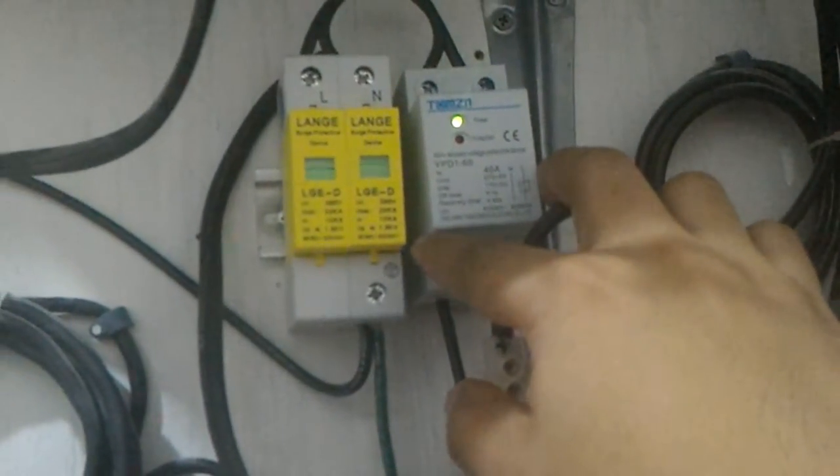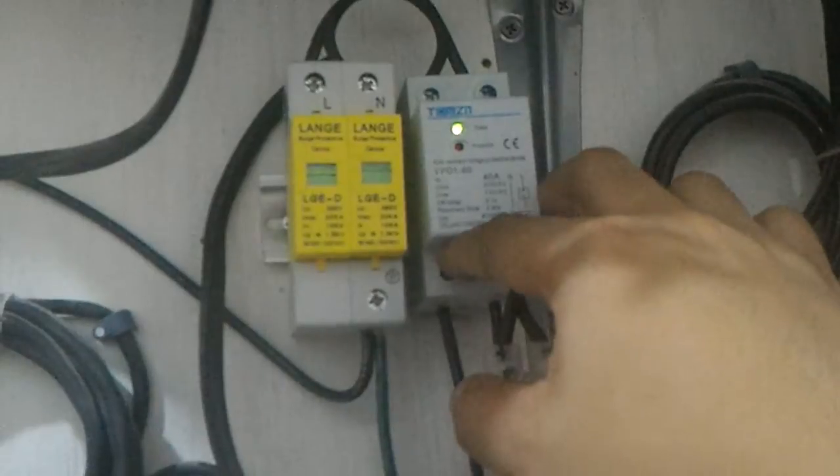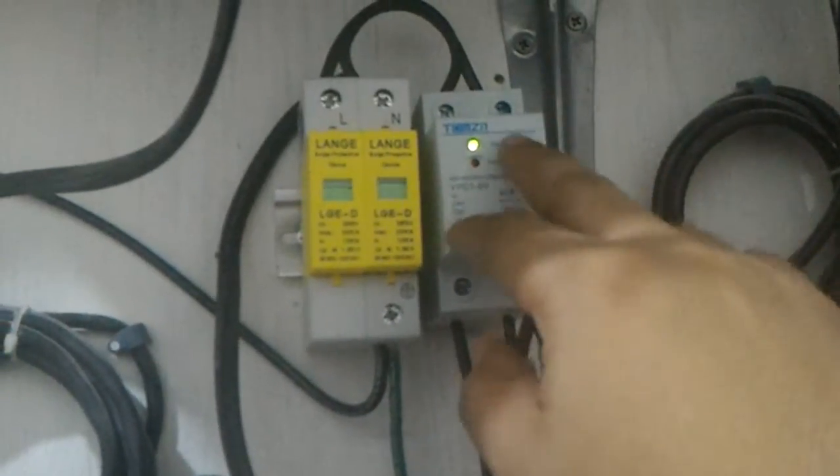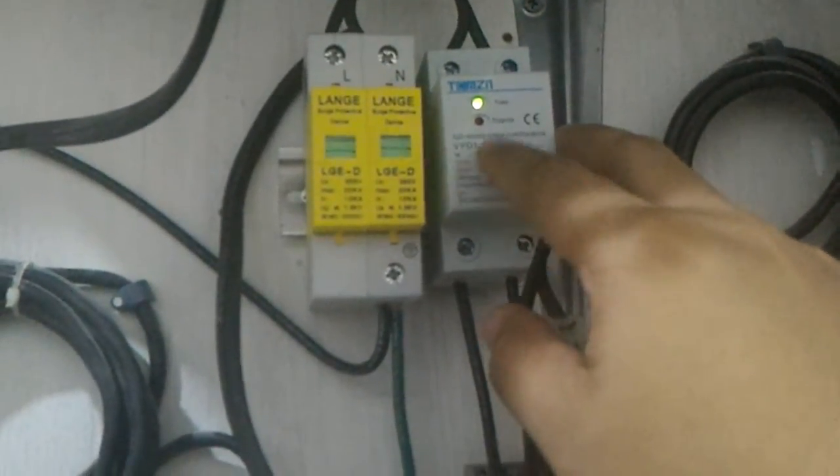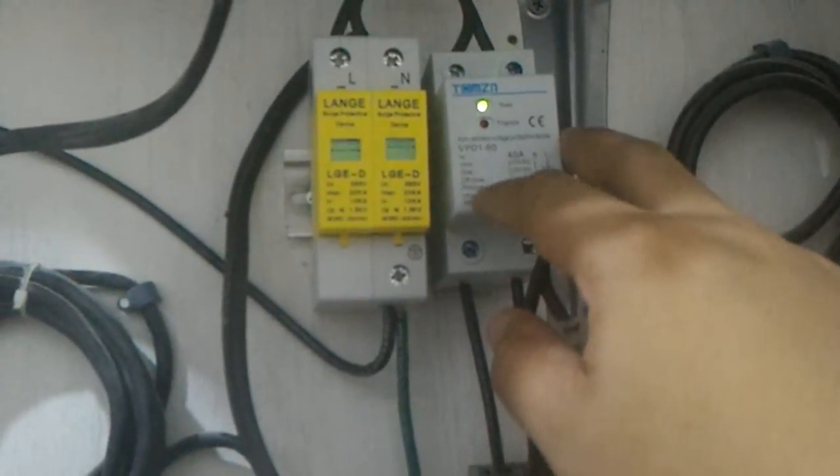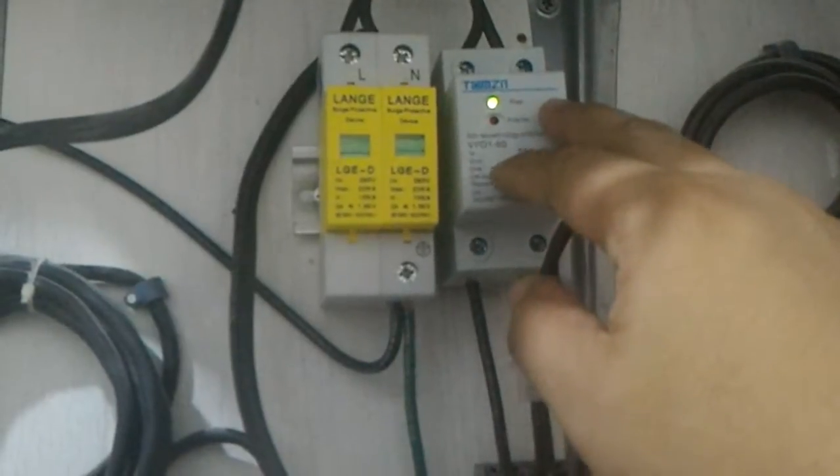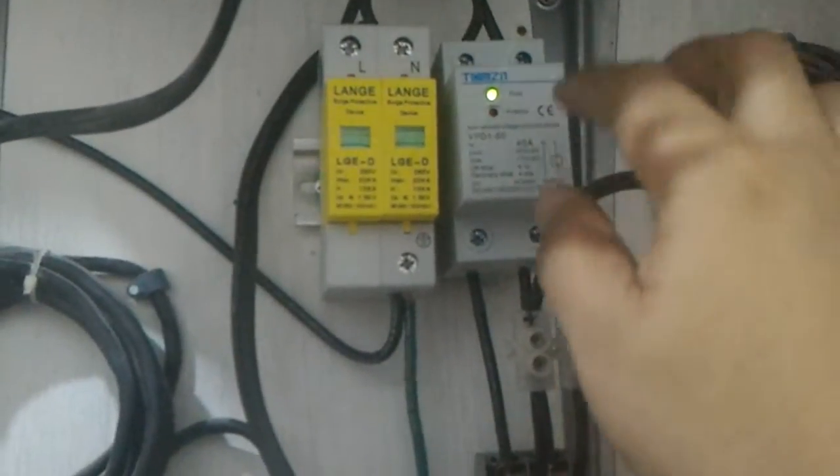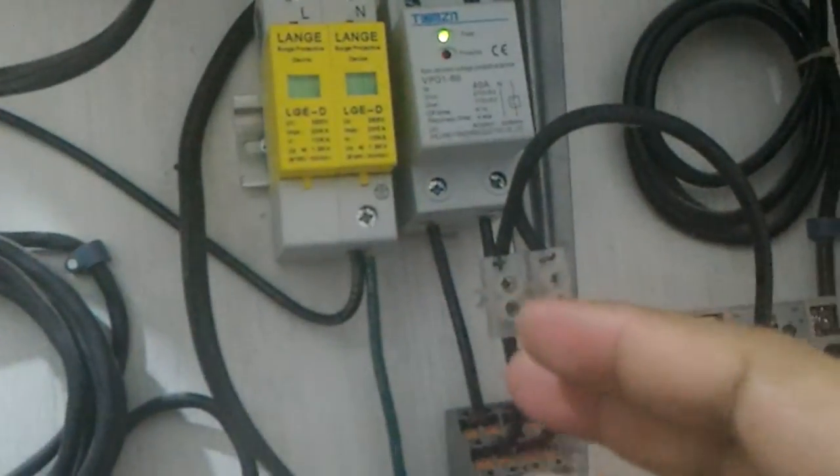When the power goes off and comes back on, it provides a one-minute time delay. It also provides over and under voltage protection—it cuts off above 270 volts and below 170 volts. It's connected to an electromechanical relay.